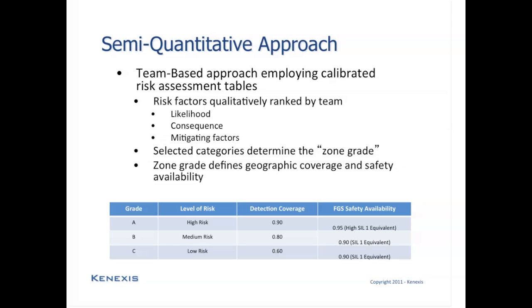In a semi-quantitative approach, you're going to use a team-based analysis of the risk that a zone poses using calibrated risk assessment tables. And those tables are going to consider the factors that will drive the risk associated with a given zone. The risk factors that are going to be qualitatively ranked by the team performing the semi-quantitative study include the likelihood of releases based on the type of equipment, the consequence of loss of containment scenarios in the zone, and what are the mitigating factors that will either decrease the risk or increase the risk given that a loss of containment event has occurred in the zone.